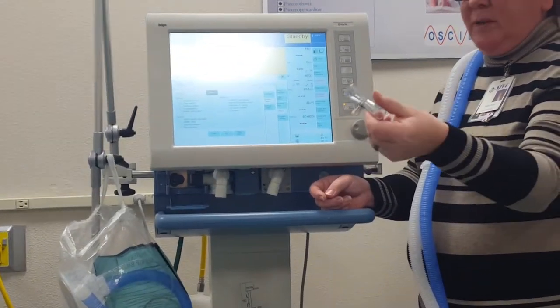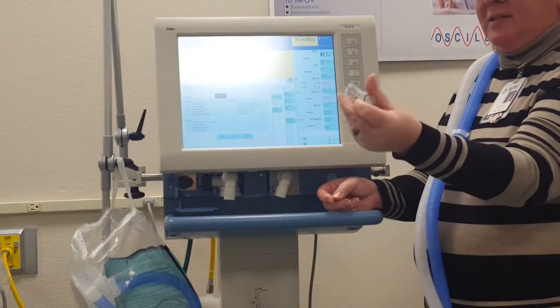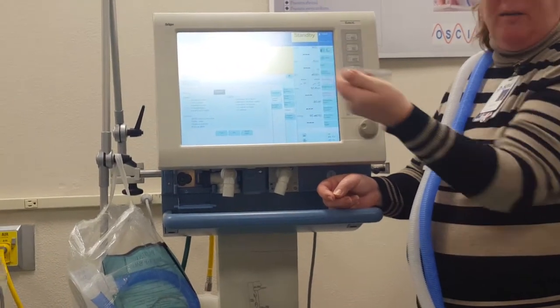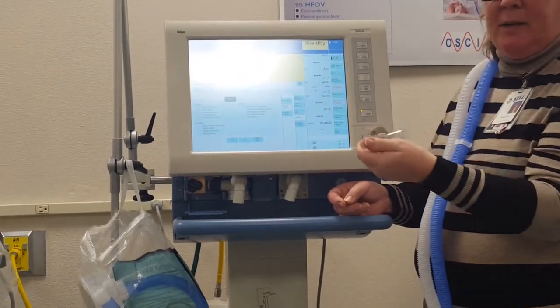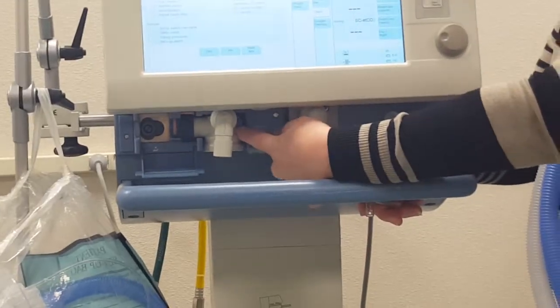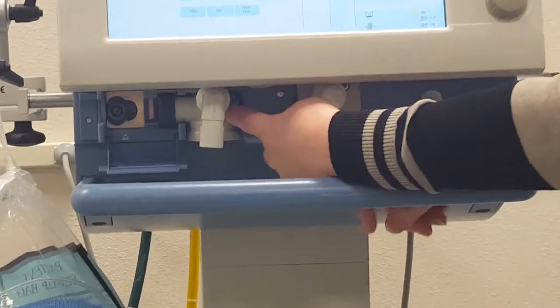So these do break, and it's called the flow sensor. If it's not letting you calibrate it, call me over, and if we need to, we'll get a replacement. They're kept away. There's a little blue tab in here that has to be pushed over. I don't know if you can get your cameras up in here, but you push the blue tab over, and then you pull this piece out.